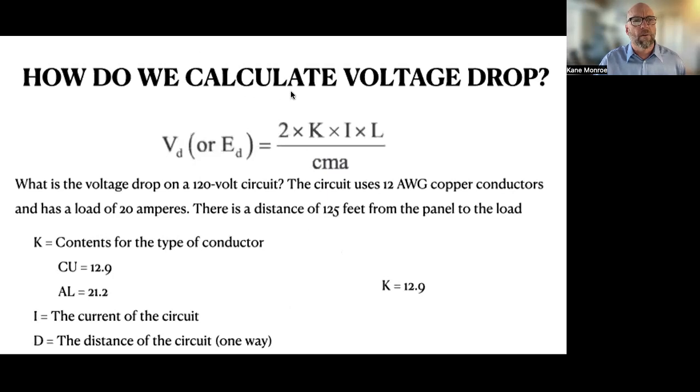So here we go. How do we calculate it? We use this formula right here. Here's the question right here. What is the voltage drop? First off, let's figure out what K is. In the question, it told us that we had number 12 copper conductors. So we're going to use 12.9 to go into the K section.